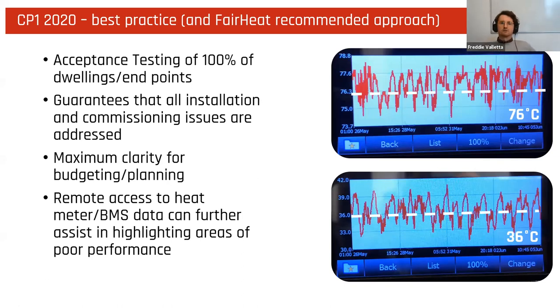As Gareth said, we're completely thrilled and proud that acceptance testing has been included within CP1 2020 as a minimum requirement. Although our recommended approach is to take this one step further. Basically, our approach is to undertake the CP1 best practice. The best practice outlines that acceptance testing should be carried out over 100% of dwellings and endpoints. This ensures that correct service levels and design return temperatures can be achieved across the network.